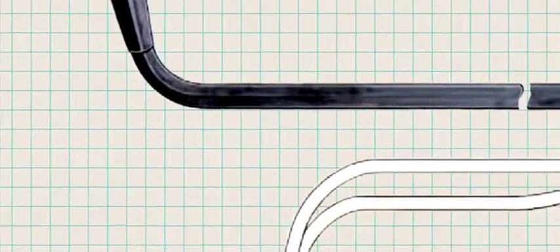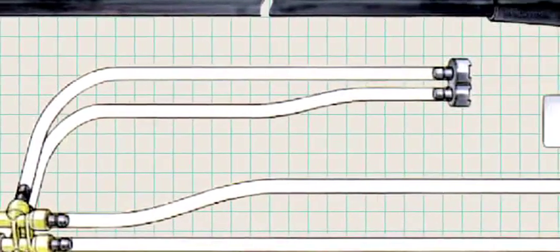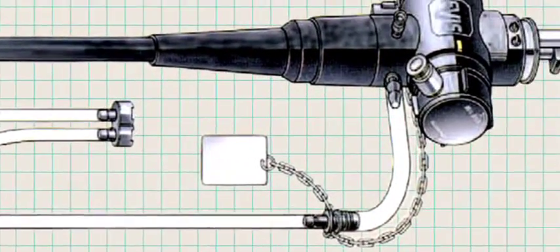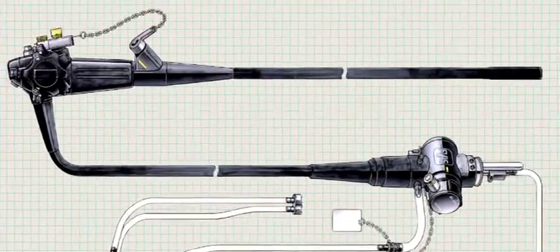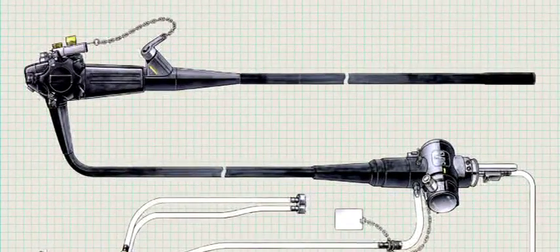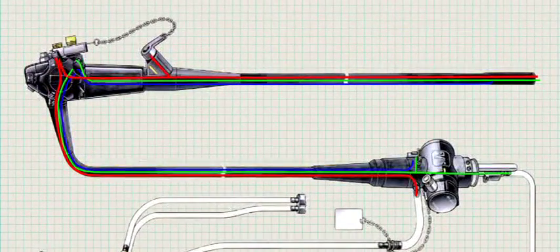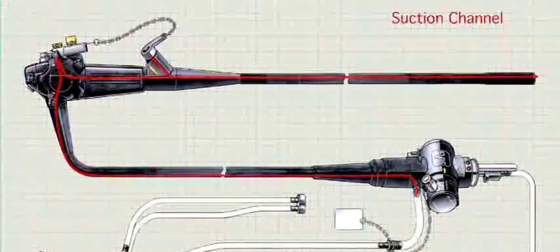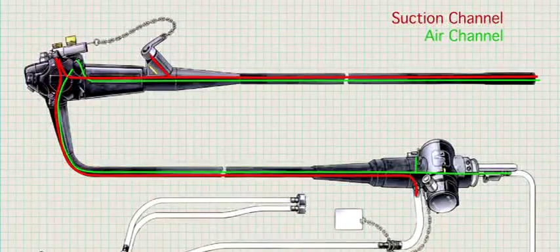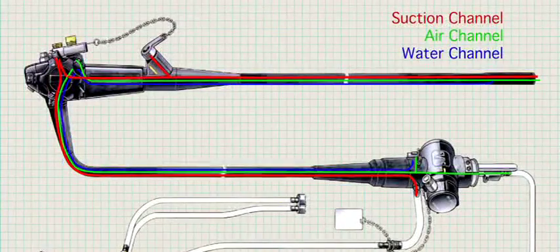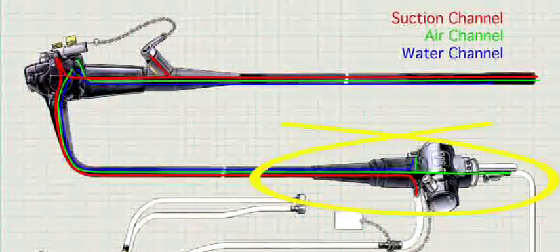A basic understanding of the internal workings of an endoscope will assist the user to properly inspect, use, clean, and disinfect these instruments. Endoscopes have long, narrow channels that make cleaning and inspection for cleanliness difficult. The suction or biopsy channel, air channel, and water channel traverse the length of the endoscope, including the insertion tube and light guide tube and umbilicus.